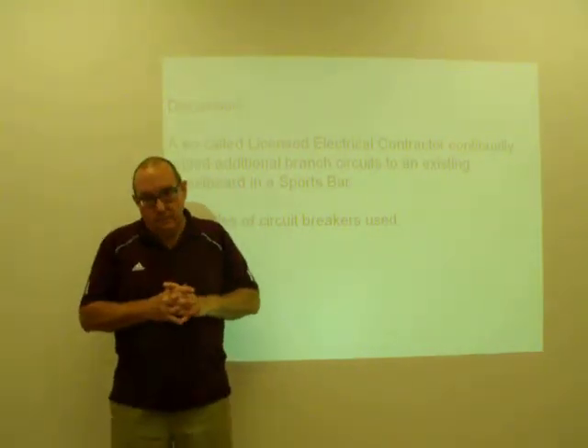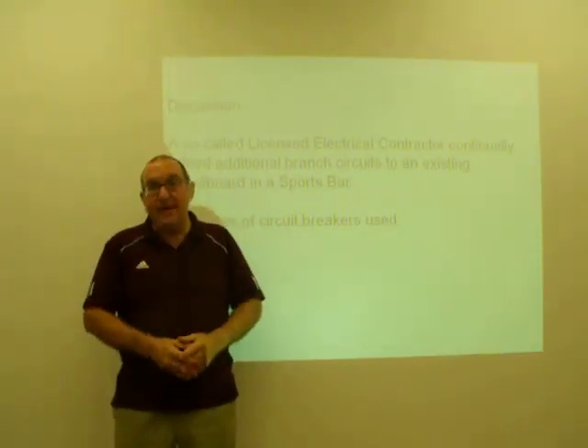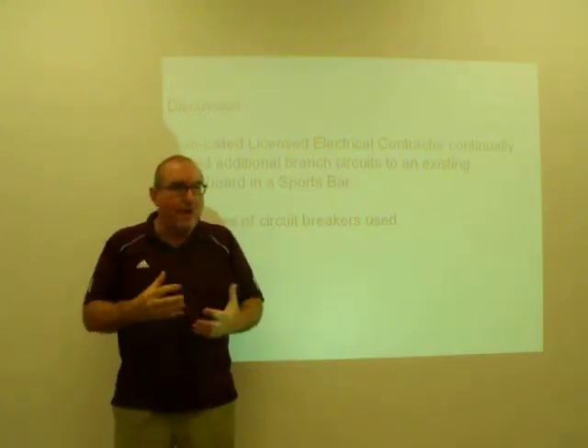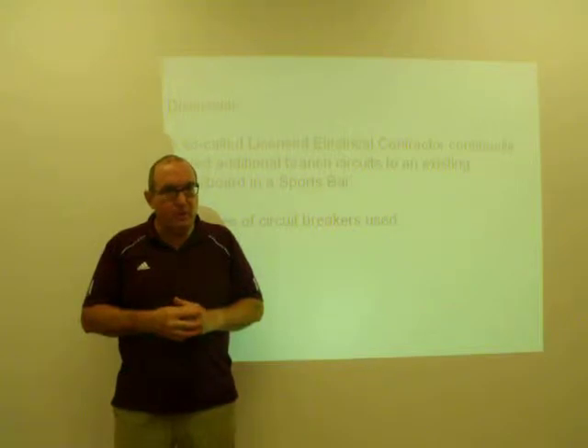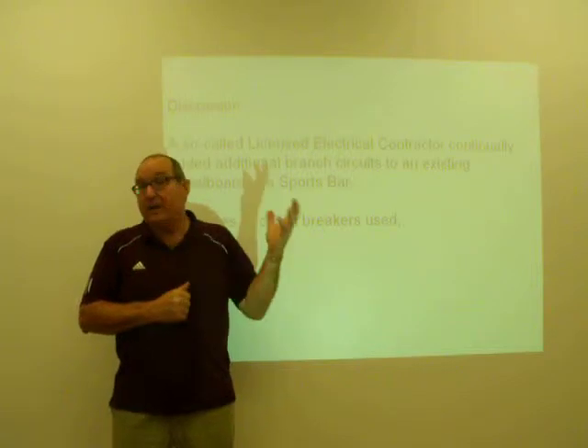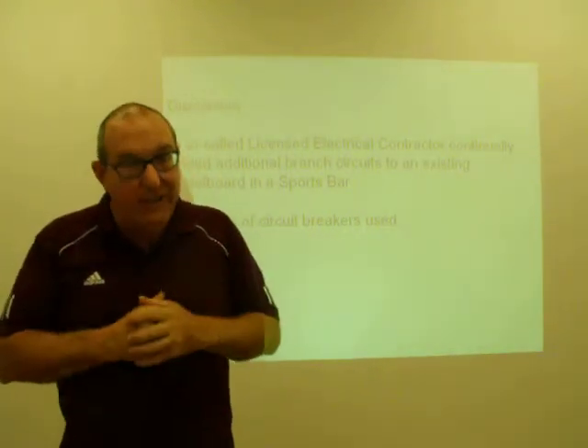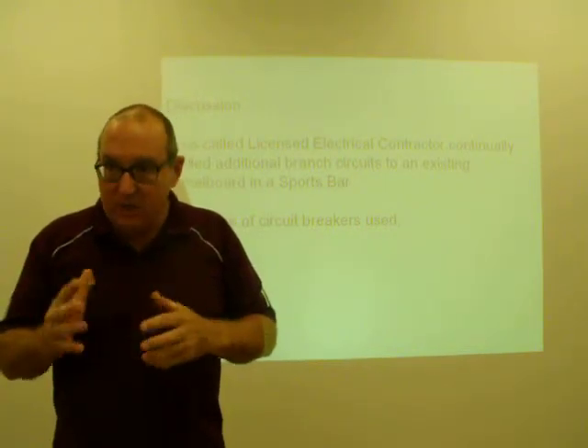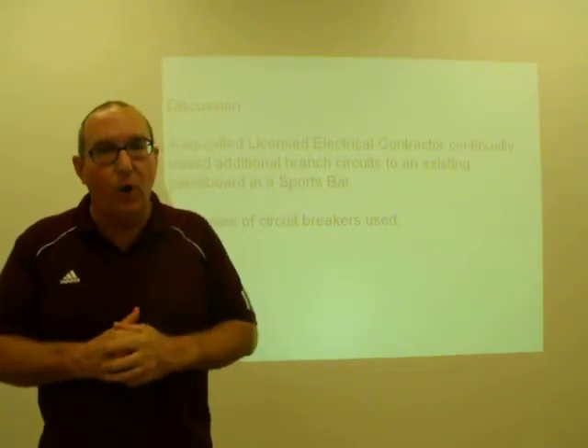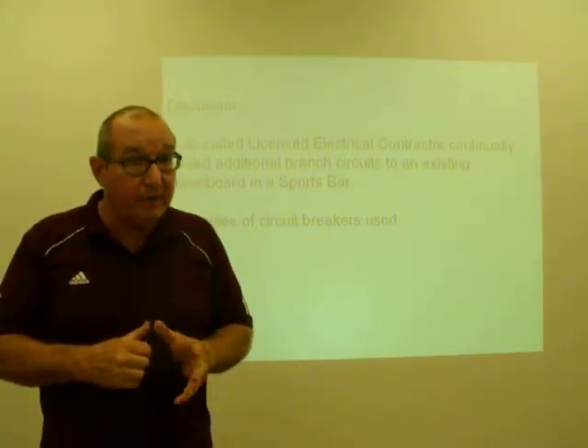So this so-called licensed electrical contractor, every time he was asked to come back and add another piece of equipment, add another circuit or something like that, he would choose to bypass the code requirements and come up with his own solution to how he could do this. So evidently he was running out of circuits. He'd exceeded the 42 limit capacity, which at that time was the limit. Those of us that are more familiar with the code know that that is no longer necessarily true, but there's a lot of older equipment out there, far more older equipment out there with the 42 circuit limitation than there is newer equipment.